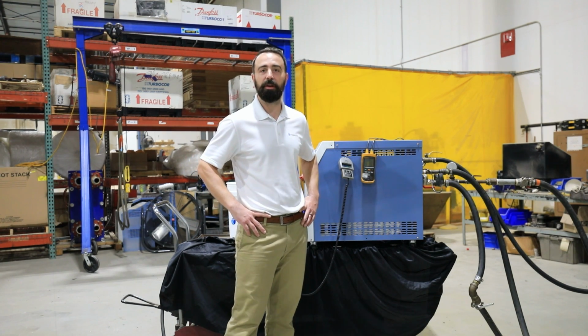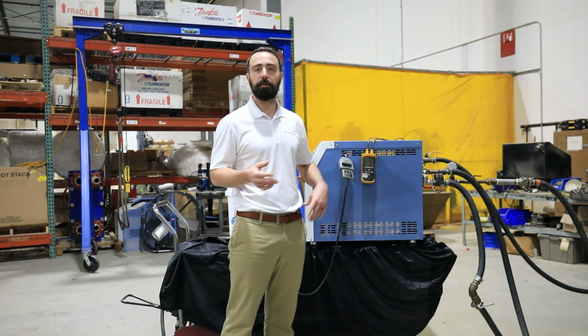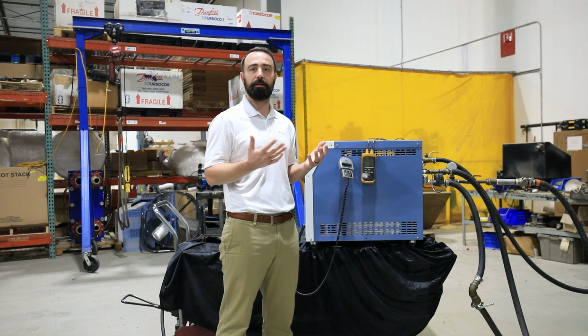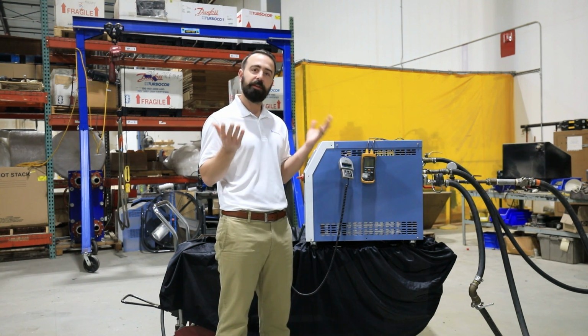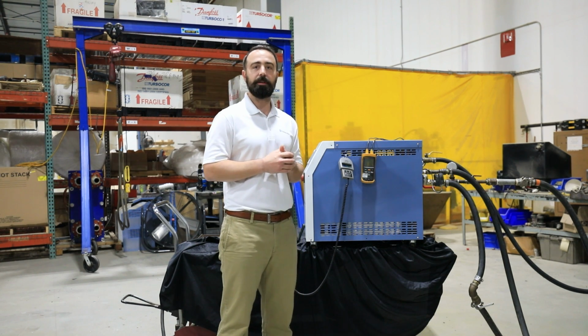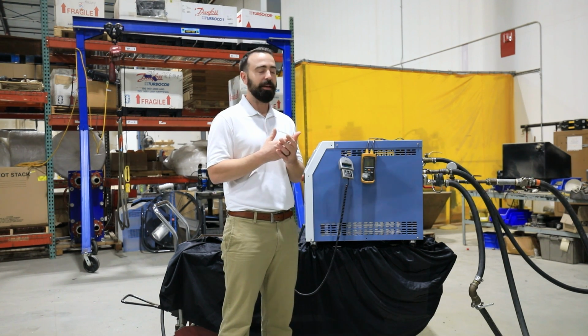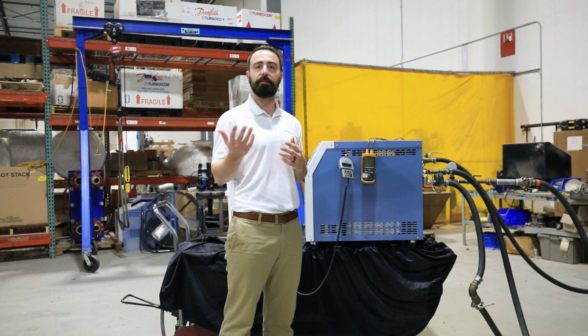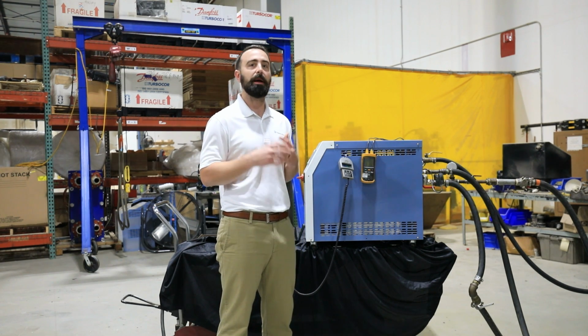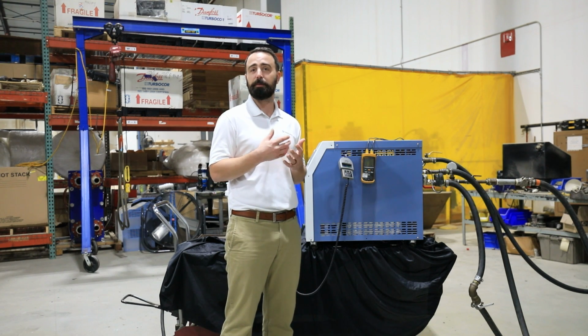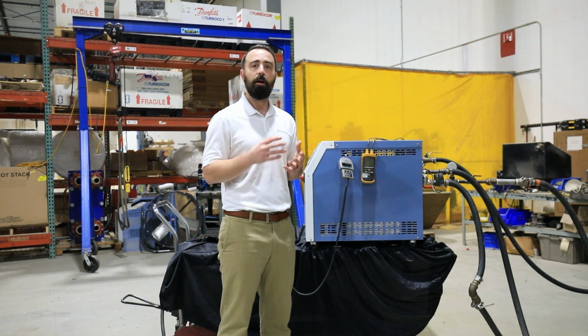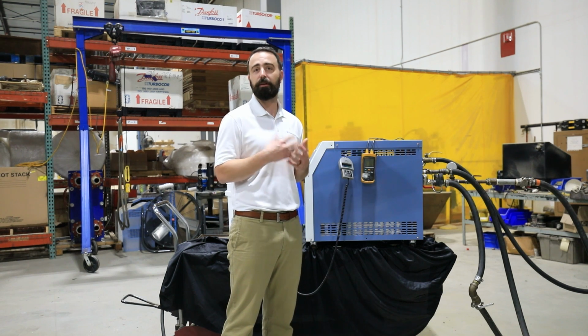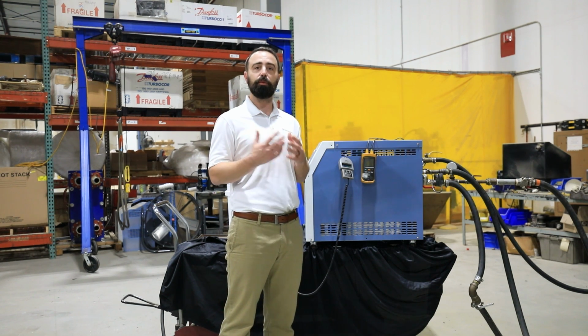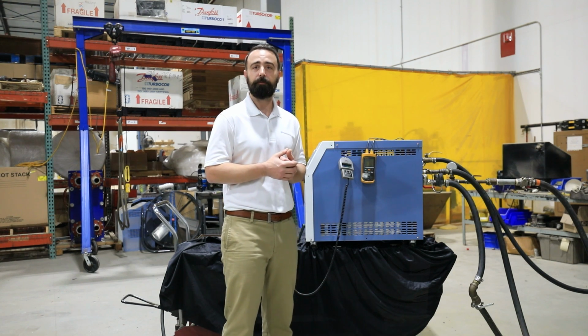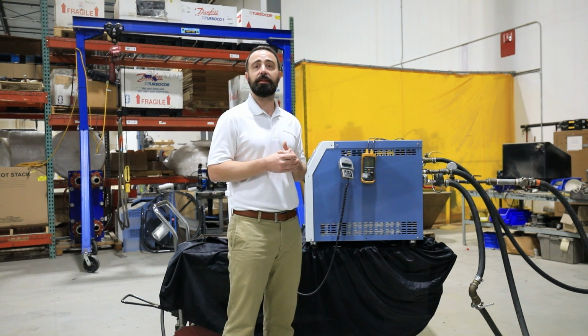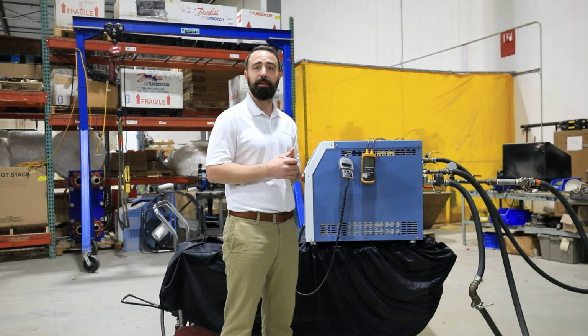Our team encounters all sorts of situations where there's not enough information available to calculate the cooling requirement theoretically. And what I mean by that is across the 50 plus different industries that we serve, oftentimes there are rules of thumb that we can use along with readily available pieces of information like a motor horsepower or a power supply rating or even the mass, material type, and temperature change of a metal. All of those can be used to calculate a theoretical cooling load based on some equations related to the specific application.